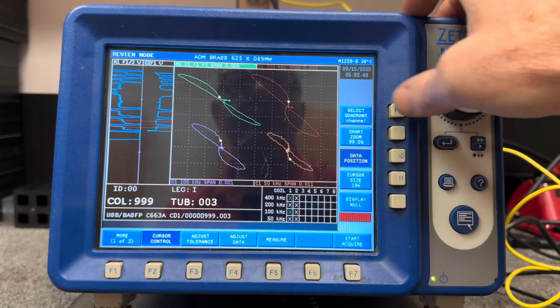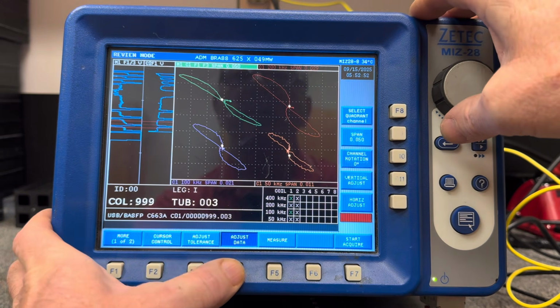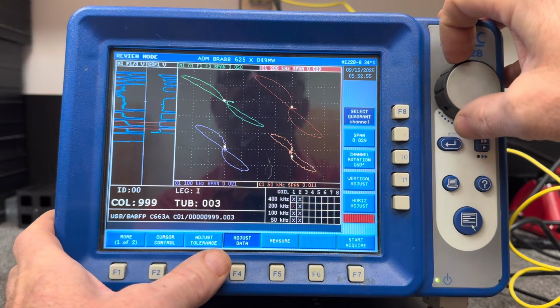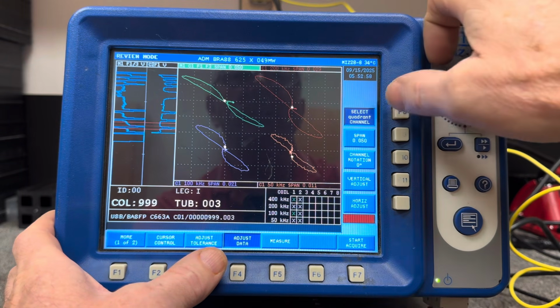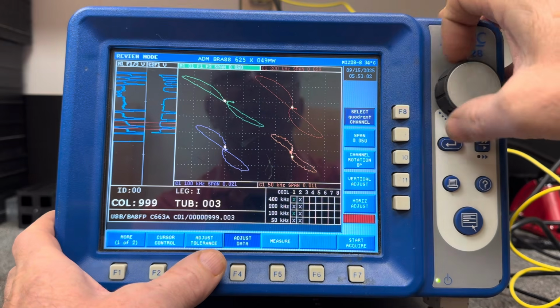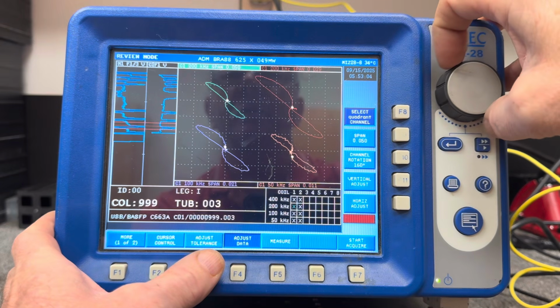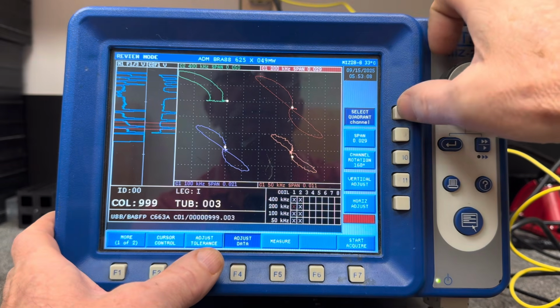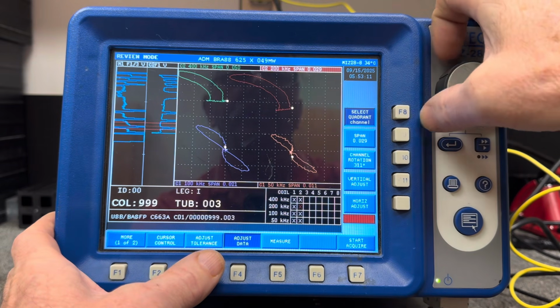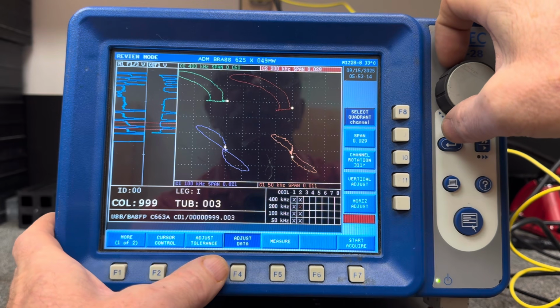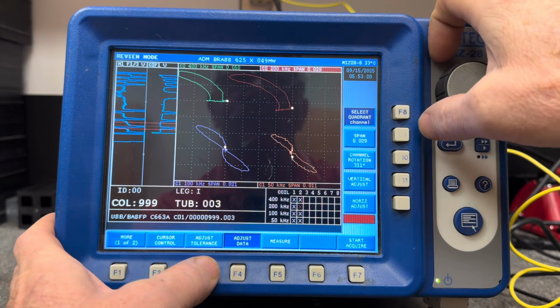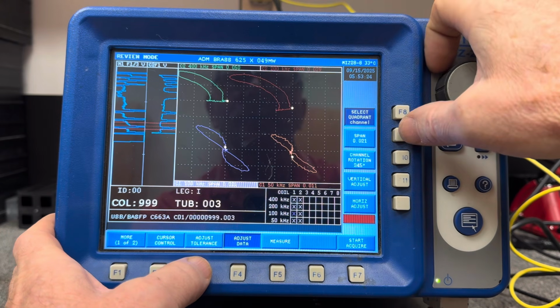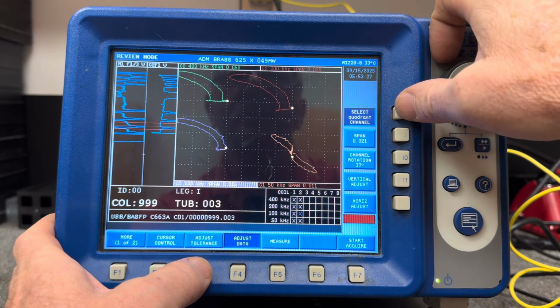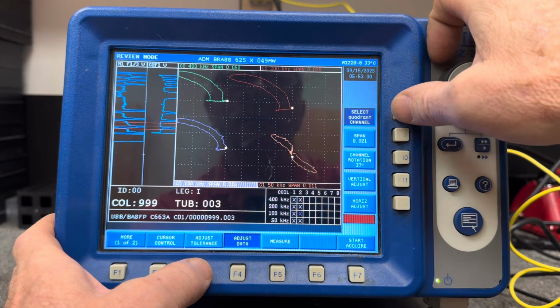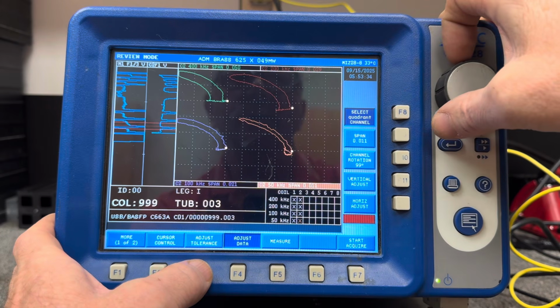And obviously this is, let's see, select quadrant, differential and absolute. So we can go over and we can put all our absolutes up here, which is important for finding gradual flaws, such as thinning, erosion, tube to tube wear, maybe a long foreign object mechanical wear scar. Let's see, we got another channel here. There we go, there's our channel. So we have 400, 200, 100. And then the last one, we'll just go real quick. So there's your absolutes.